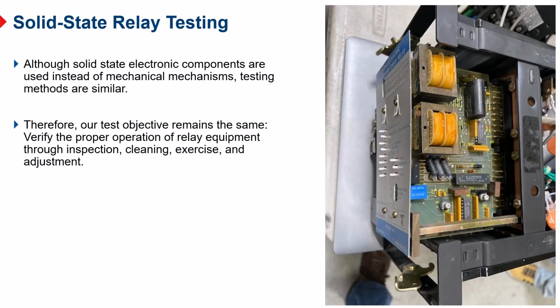Bad thing is, over time, in a hot, humid, or dirty environment with wide temperature changes, just like what you'd find in a relay room, the traces actually fall off the board eventually. So this first generation of relays after electromechanical, the solid state relays, had a pretty bad reputation for reliability. Also, one of the issues was there were no testing standards for electromagnetic interference.